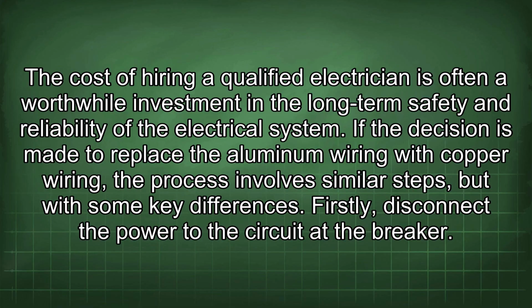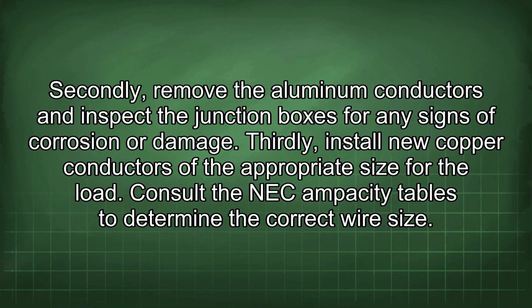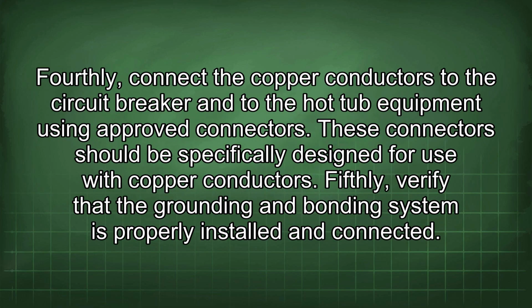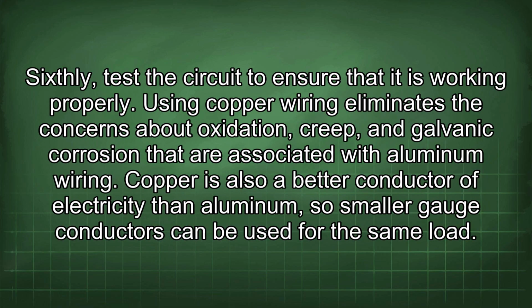If the decision is made to replace the aluminum wiring with copper wiring, the process involves similar steps but with some key differences. Firstly, disconnect the power to the circuit at the breaker. Secondly, remove the aluminum conductors and inspect the junction boxes for any signs of corrosion or damage. Thirdly, install new copper conductors of the appropriate size for the load. Consult the NEC ampacity tables to determine the correct wire size. Fourthly, connect the copper conductors to the circuit breaker and to the hot tub equipment using approved connectors. These connectors should be specifically designed for use with copper conductors. Fifthly, verify that the grounding and bonding system is properly installed and connected. Sixthly, test the circuit to ensure that it is working properly.